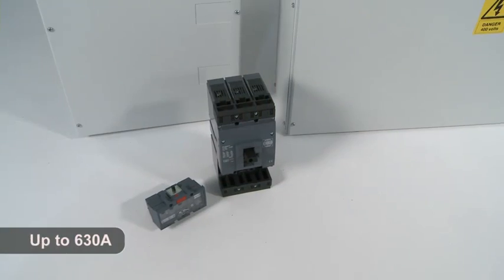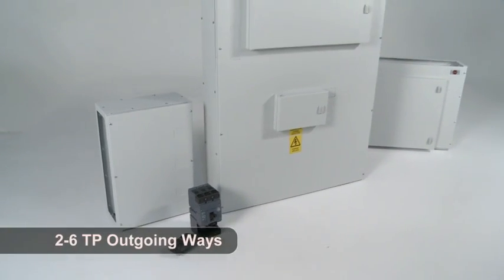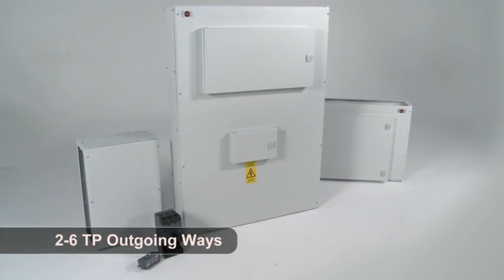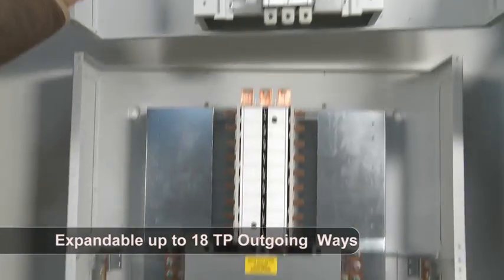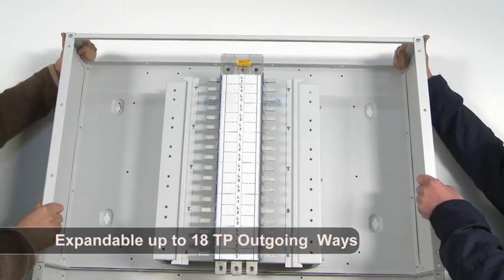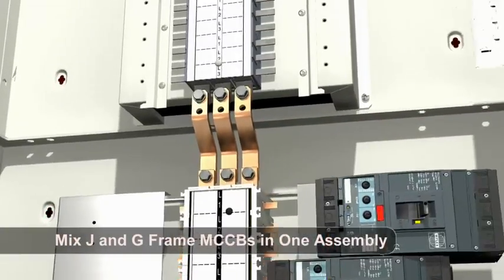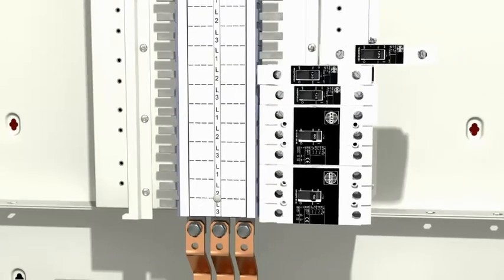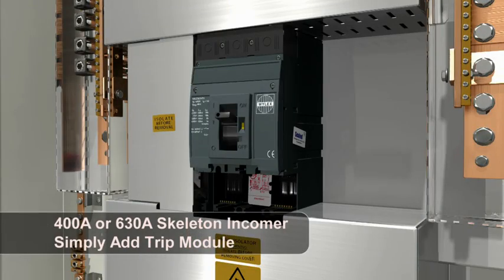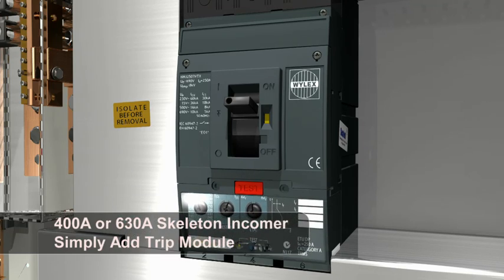The NH250 system includes panel boards up to 630 amps with outgoing MCCBs from 2 to 6 triple pole ways. However, unlike the NH125, the NH250 system is expandable up to 18 triple pole outgoing ways which can include G-frame MCCBs. This gives the installer the flexibility to mix J and G-frame MCCBs in one assembly. These panel boards are supplied complete with a 400 amp or 630 amp skeleton incomer to which the installer simply adds a trip module or electronic MCCB module.